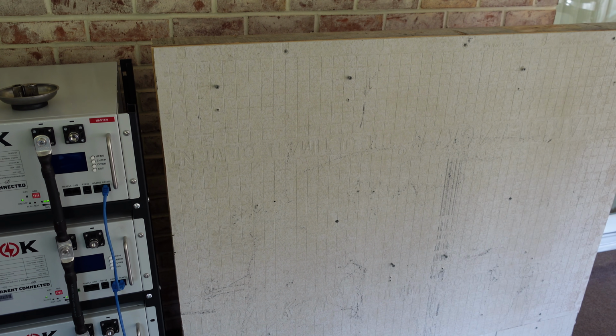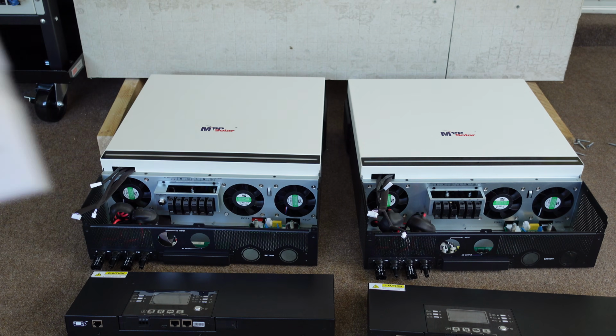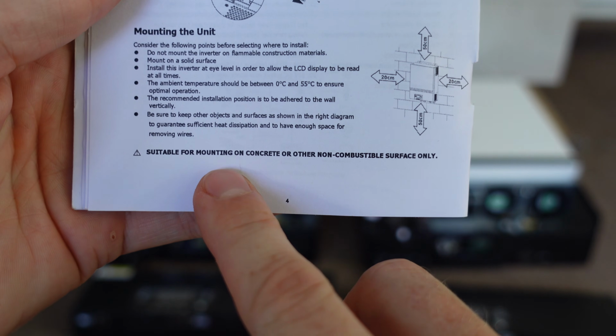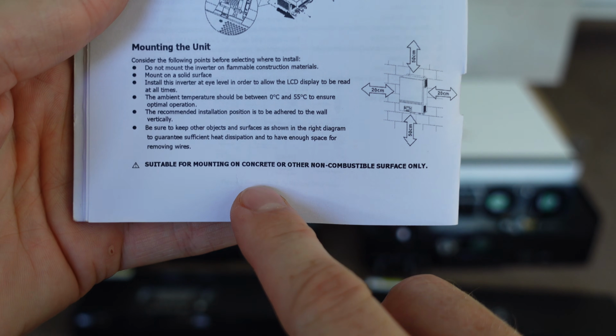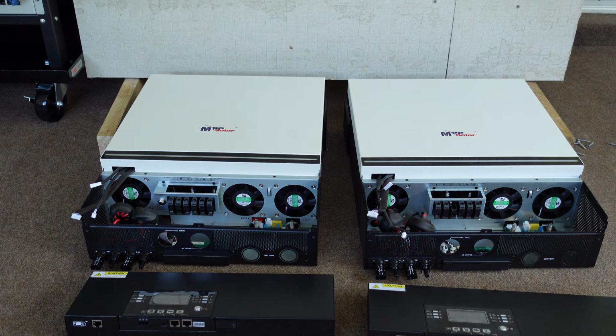And I'll be mounting them up on this temporary wall structure here. This is 5/8 plywood, I think, and then I have it covered with 1/4 inch of cement board the whole way around. Now the use of the cement board is per the user's manual, where it says it's suitable only to be mounted on non-combustible surface. That means you're not supposed to mount this inverter directly to wood.